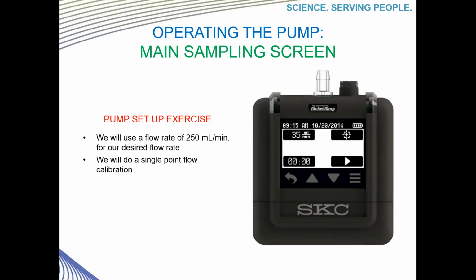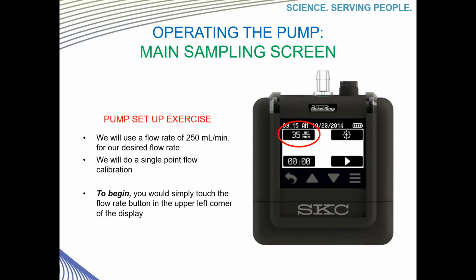I'm going to walk through changing the flow rate from where it is now, which is 35 milliliters per minute, which you can see in the upper left-hand corner of the display, to a flow rate of 250 milliliters per minute. Then we will do a single point calibration as well. To begin, in order to adjust the flow rate, you would need to touch the flow rate button in the upper left corner of the display.